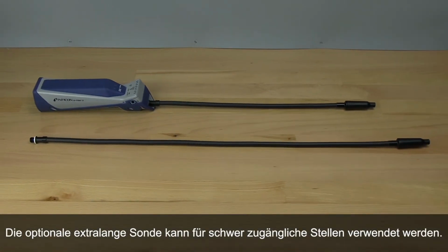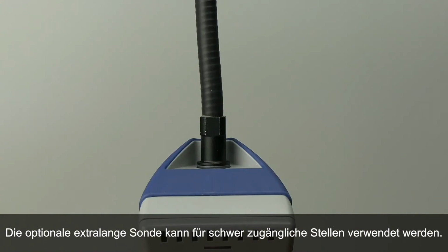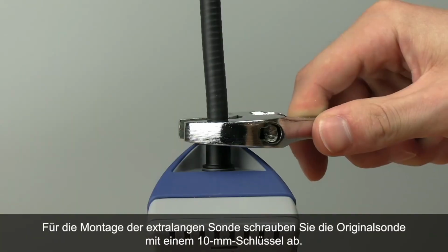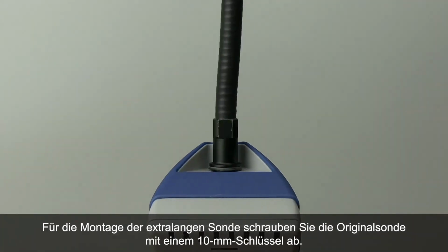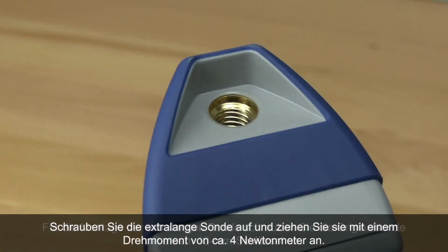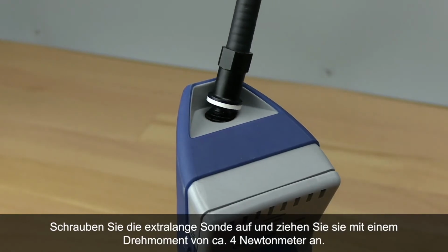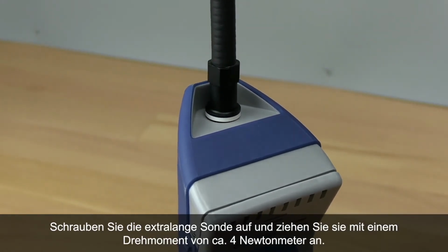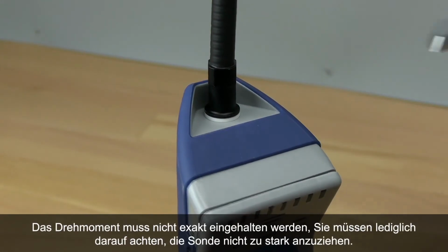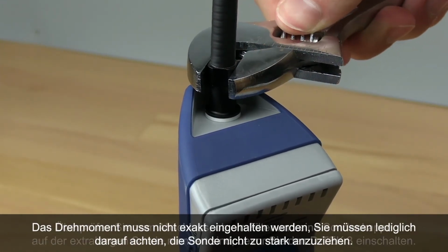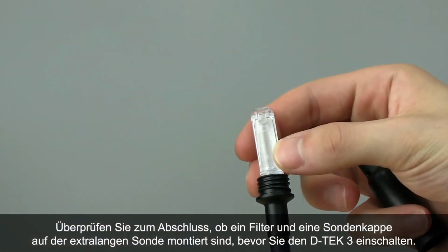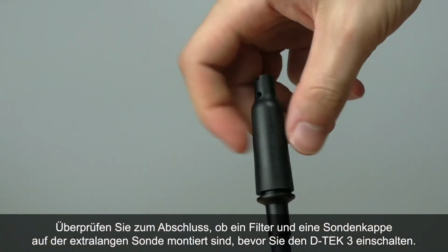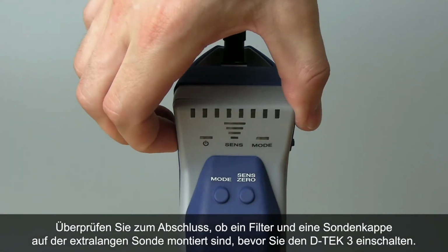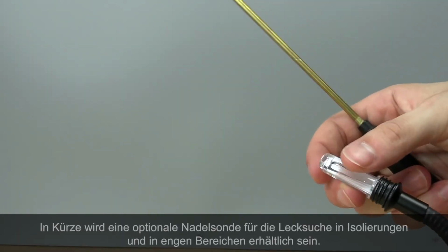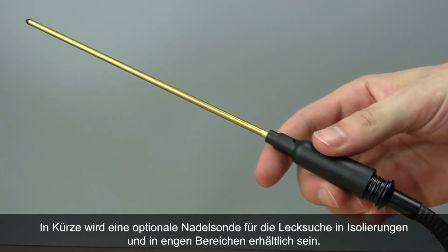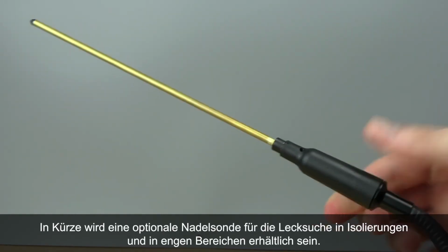The optional extra long probe can be used for those hard to reach places. To install the extra long probe, unscrew the original probe using a 10mm wrench. Screw the extra long probe on and torque to about 35 inch-pounds or 4 Newton-meters. Torque doesn't have to be exact, just make sure you don't over-tighten it. Finally, make sure you have a filter and probe cap installed on the extra long probe before turning D-TEK-3 on. An optional needle probe will be available soon for leak checking in insulation and tight spaces.